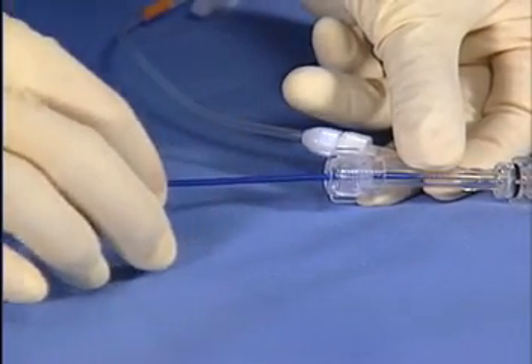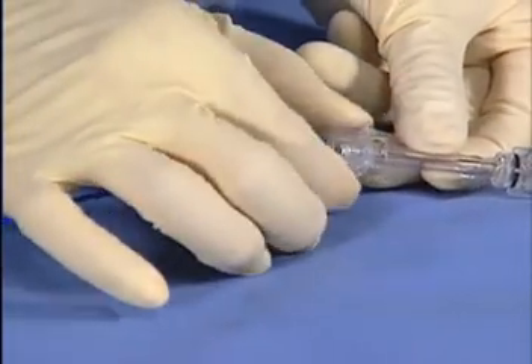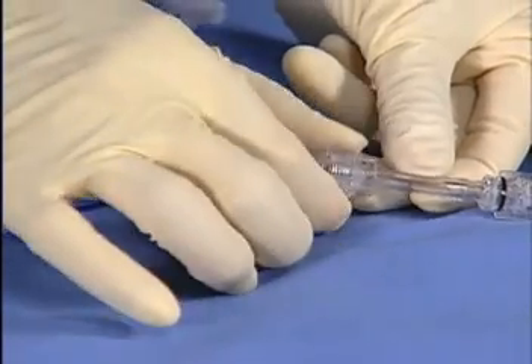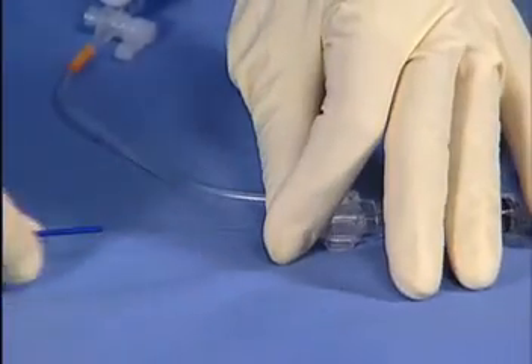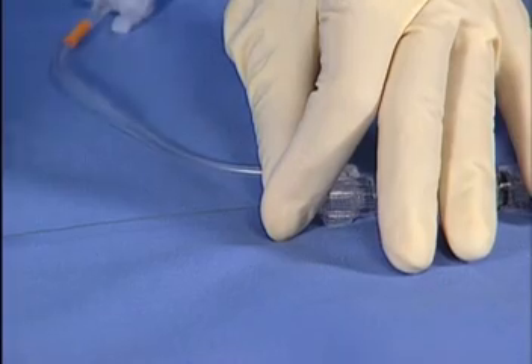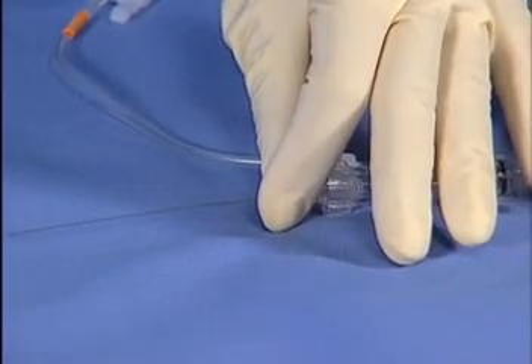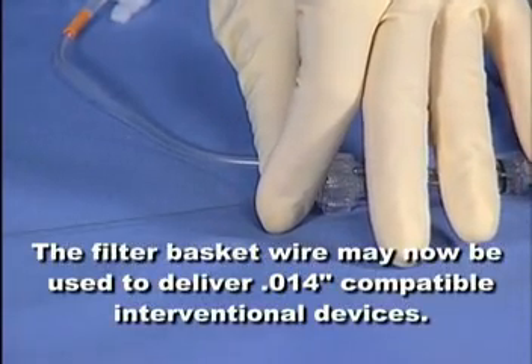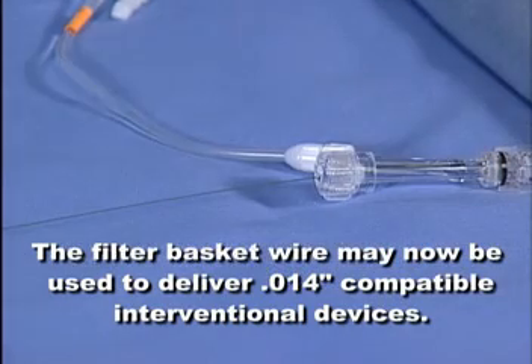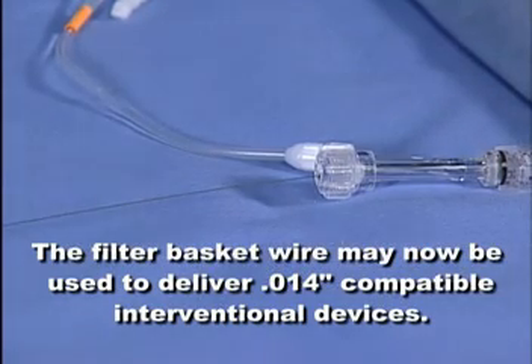Remove the introducer tool from the hemostasis valve and tighten down the valve if necessary. Remove the torque device, delivery sheath, and introducer tool from the wire. The filter basket wire may now be used to deliver 0.014 inch compatible interventional devices.